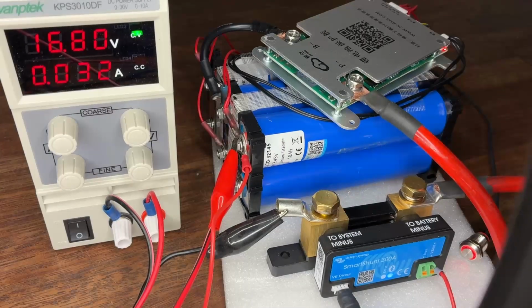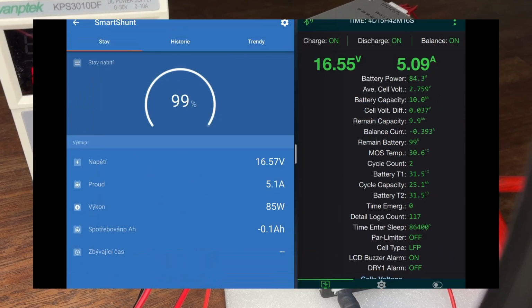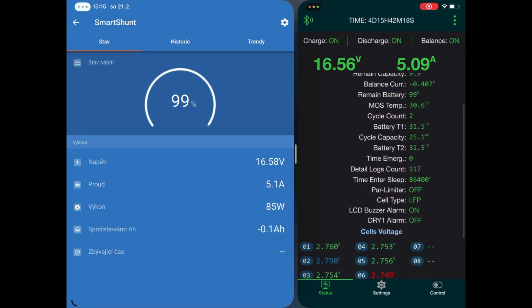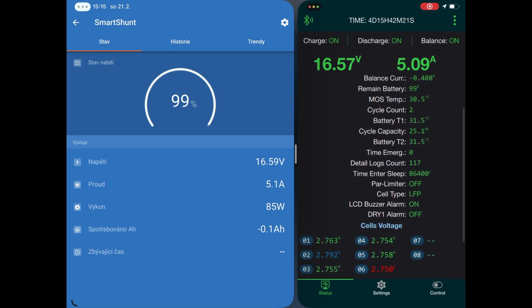Now, we will charge the battery to 16.8 volts, which is the maximum, meaning 2.8 volts per cell. The battery is now charged. Here we see the battery just before its first full charge. The cells are balancing, and we can monitor their individual voltages. As you can see, we are running a 6-cell setup here. Once the cells hit the 2.8 volt limit, the BMS will cut the power to prevent overcharging.